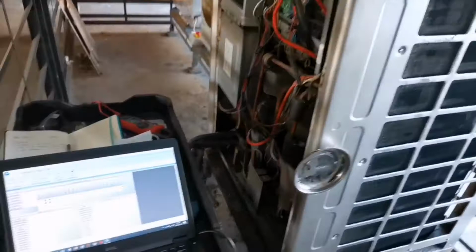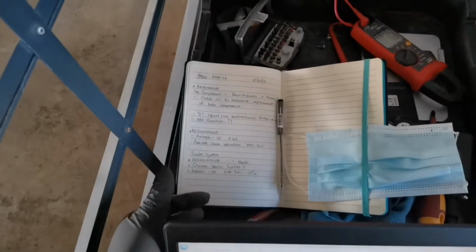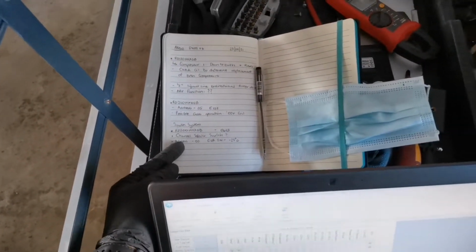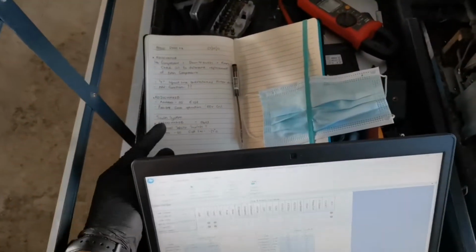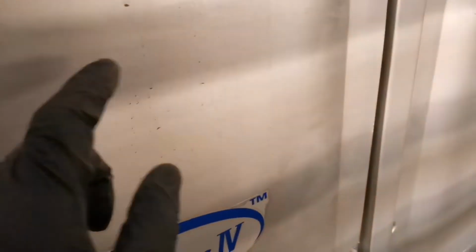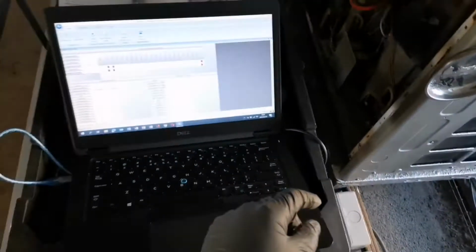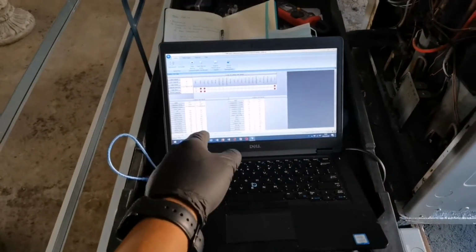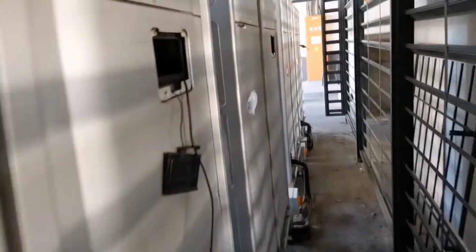You guys are getting some bonus video footage today, and here are my notes so far. In fact, we are doing some repairs on this unit as well, but on the inside, on the indoor units. One of the respective indoor units linked to the system has an electronic expansion valve coil that's gone bad. Still in oil withdrawal. You guys are getting some great footage today.